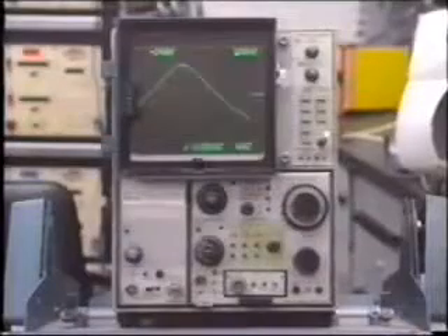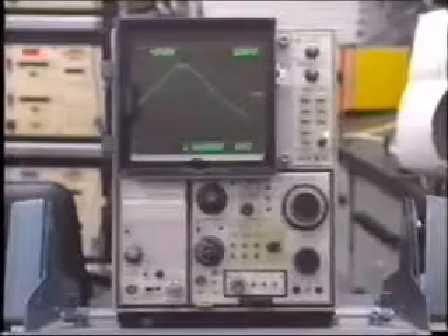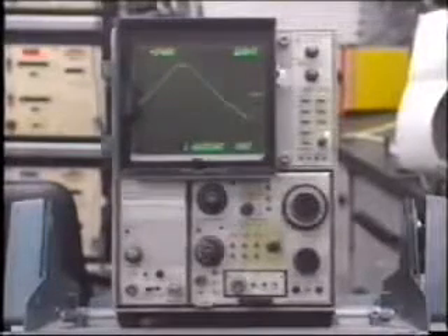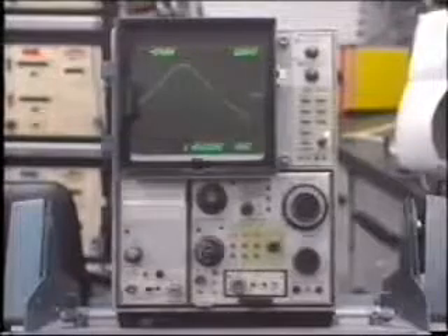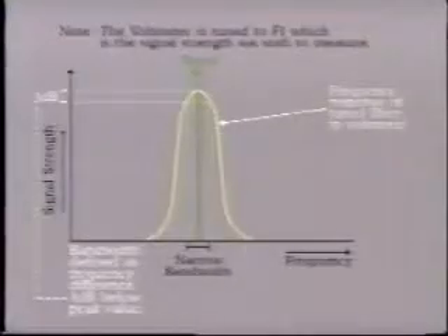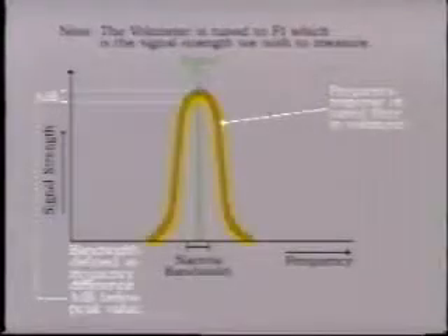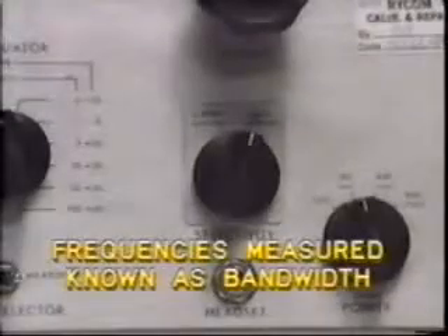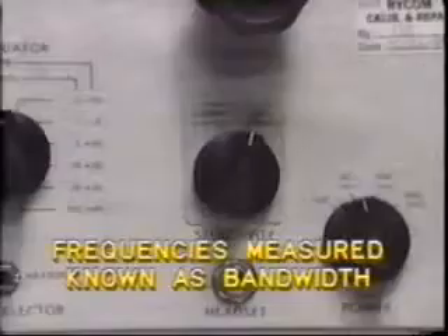In this case, a spectrum analyzer may be used to examine the signal across a wide frequency range so as to detect the presence of unsuspected additional signals. When the signal frequencies are known, then a selective voltmeter can be used to check the signal strength at any selected frequency. In practice, the instrument is set up to respond to a band of frequencies either side of the selected frequency. The selective voltmeter actually filters out all other frequencies. The range of frequencies measured is known as the bandwidth.